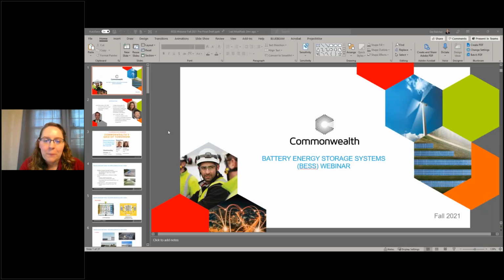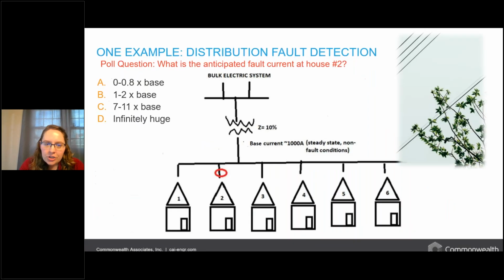I'll just explain what's happening in our picture. So as a reminder, in a traditional power system, what we think about is having this large supply of generation that's feeding the transmission grid. That's also known as the bulk electric system. There's lots and lots of power being generated, but by the time it's getting closer and closer to our communities, we might see something like 1,000 amps flowing through a transformer on a typical day, coming into our local distribution network, distribution community. And in our example on the screen, we're tapped into that large transmission and generation system, and a tree falls on one of our distribution lines. One of our wooden telephone poles makes contact with the tree.